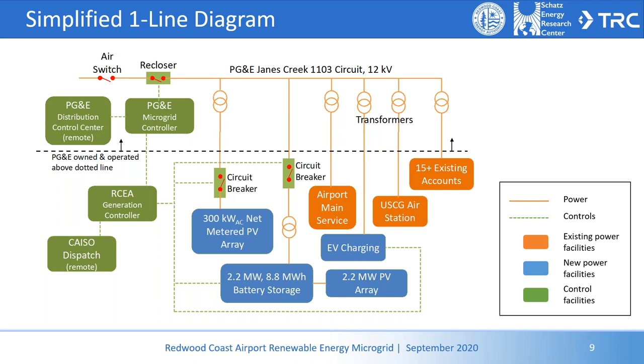You'll see in those green boxes, the two to the right: the one above the line says PG&E microgrid controller, the one below the line says RCEA generation controller. This is basically the microgrid controller, and this could have been done with a single controller, which actually would have been a bit simpler and lowered our upfront cost a little. However, we decided to bifurcate this into two separate hardware controllers with two separate sets of software.